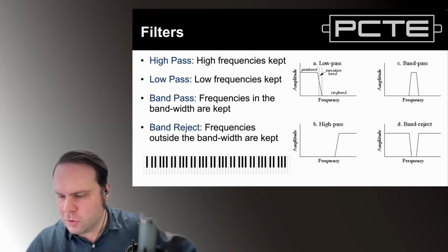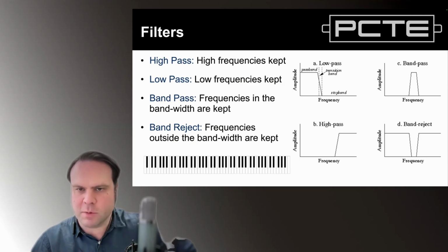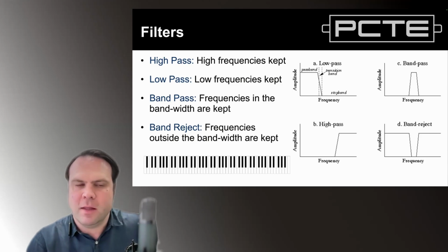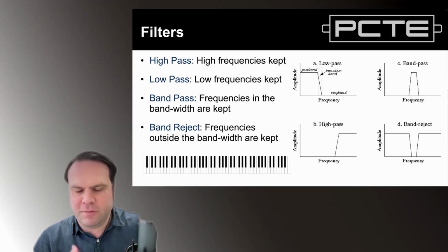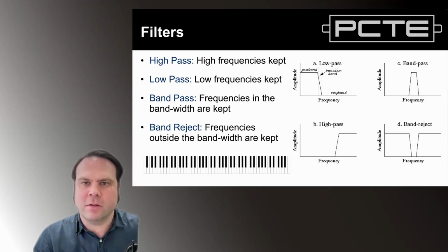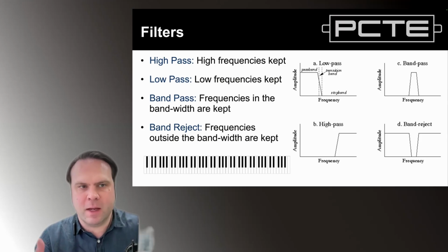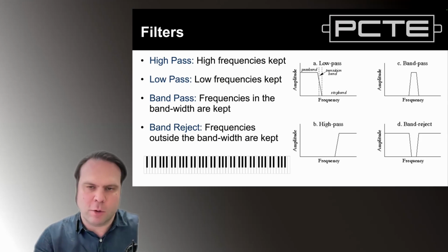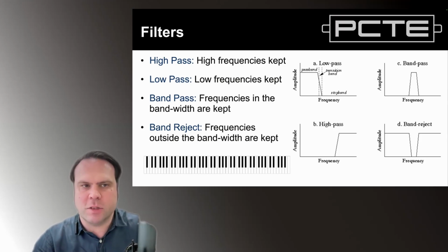And if you look at your PI8000 software or your CDG software, there's going to be a couple of filters. You'll always have access to a high pass filter in impact echo devices, and you'll also have the ability to choose a low pass filter, or with some of the Olson equipment, because they're very flexible, they'll also offer band pass filtering.